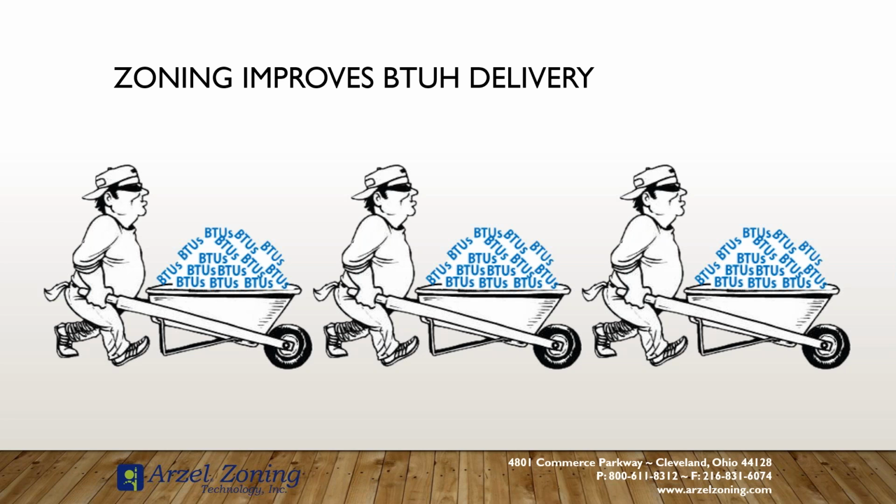But we really want to stay away from micro zoning, because if we take those zones down too much, we push our static too far, we create nuisance issues with noise for our customers, and we potentially damage our equipment. So we have to be careful when we are applying zoning. We don't want to push it so far that we're going to damage the equipment. We also don't want to push it so far that we create a nuisance issue for our customers.